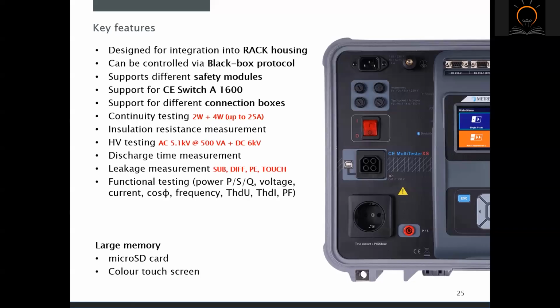shock. The CE Switch A1600 is an active multi-channel switch intended to run auto sequences or single tests on electrical equipment in combination with the master test instrument. Different connection boxes can also be used to cover different applications. The built-in feature of connection boxes is that they are coded to prevent applying too high a test voltage to their inputs. Of course, the test system is supporting continuity testing with 2-wire or 4-wire test method.